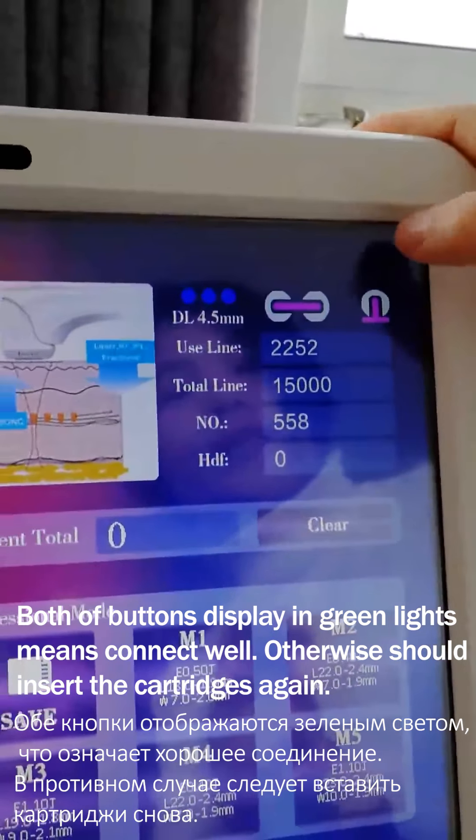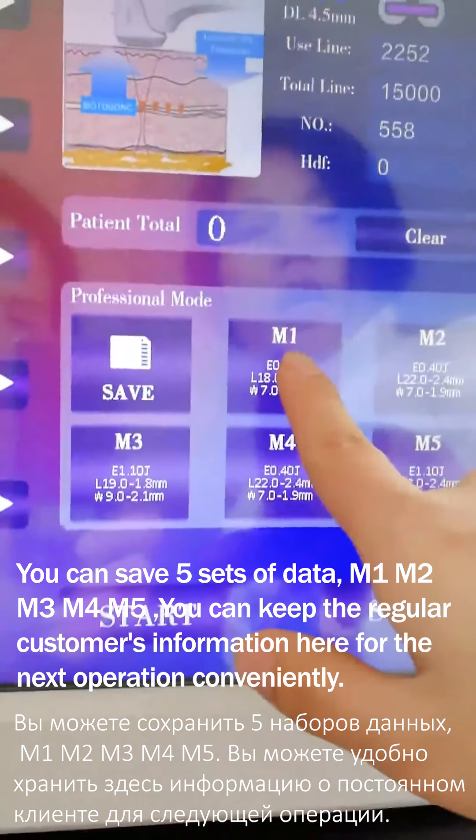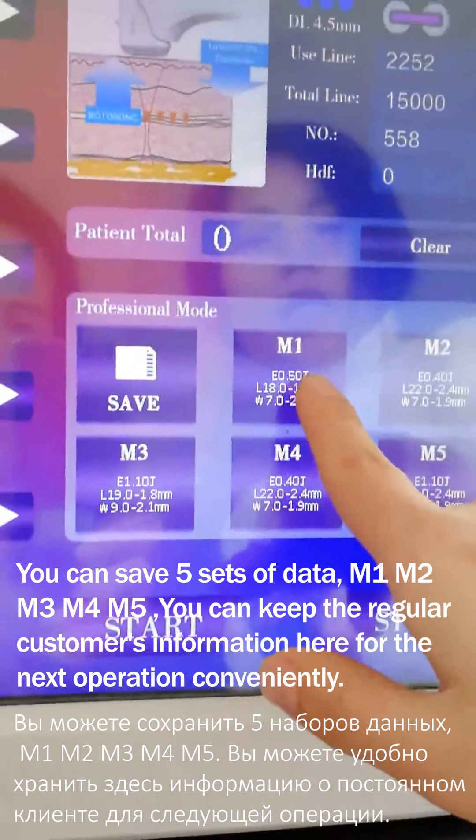The patient total is the shots used in the current treatment. There are 5 modes we can save. Usually, we can adjust them according to the customer's demand. If a customer regularly comes for treatment, we can set and save their parameters. For example, select mode 3, press save, then adjust the parameters. Click mode M3 and it's saved. Energy and parameters are stored, so next time we can directly recall it and do the treatment for the client.